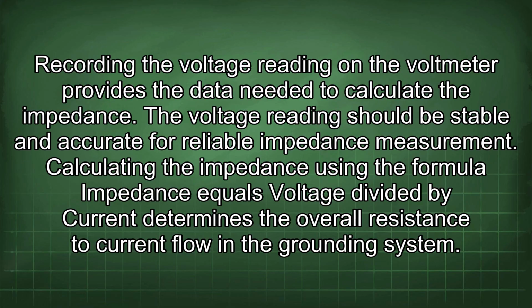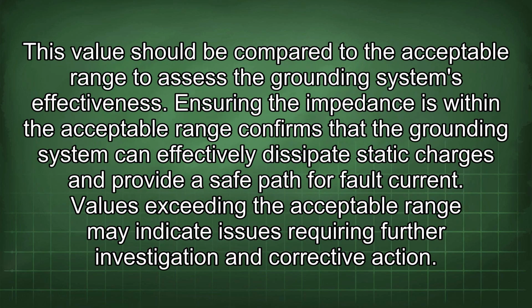Calculating the impedance using the formula impedance equals voltage divided by current determines the overall resistance to current flow in the grounding system. This value should be compared to the acceptable range to assess the grounding system's effectiveness. Ensuring the impedance is within the acceptable range confirms that the grounding system can effectively dissipate static charges and provide a safe path for fault current. Values exceeding the acceptable range may indicate issues requiring further investigation and corrective action.